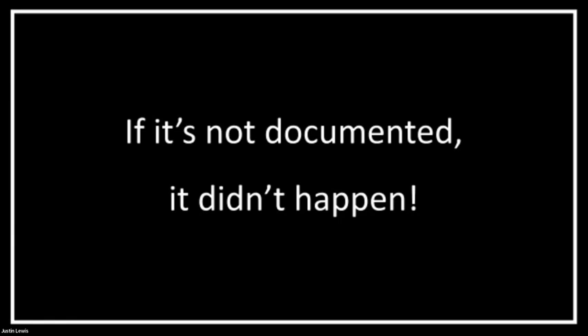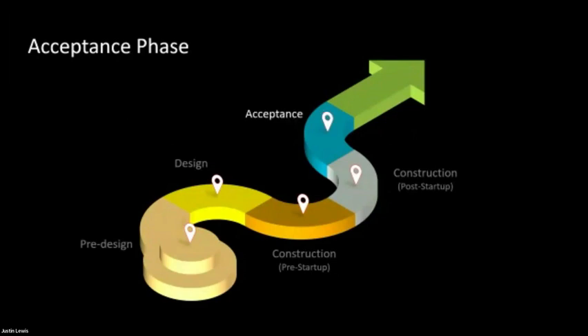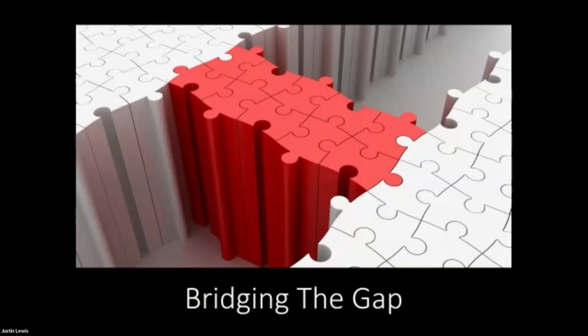Now, this brings us to the acceptance phase. The base TAB scope should be closing out, and we should be working on punch list items and fine-tuning the system at this point. We're also going to be working very closely with the commissioning team to validate the system and complete functional performance testing. In this final stage of construction, we often find hidden issues and subtle limitations of the system or design. The insight of the TAB contractor can often cut through some of the nuance of problems that may overwhelm the team at large. With our experience and depth of knowledge with not only system limitations, but the relationships and interactions with associated systems, the TAB contractor may help resolve issues more effectively.